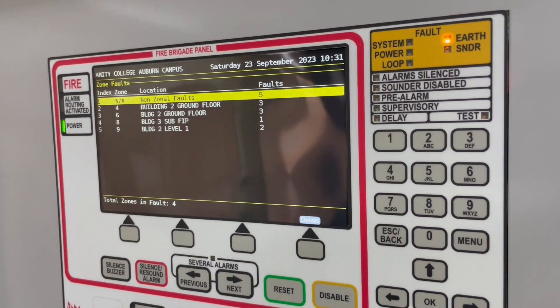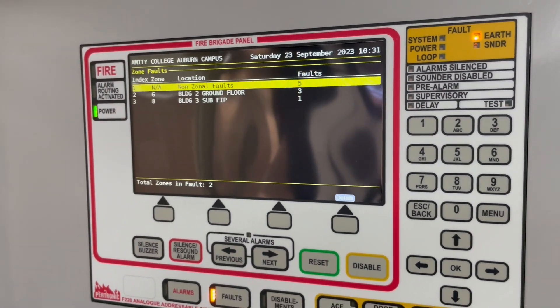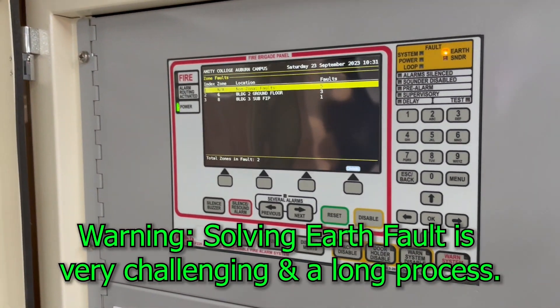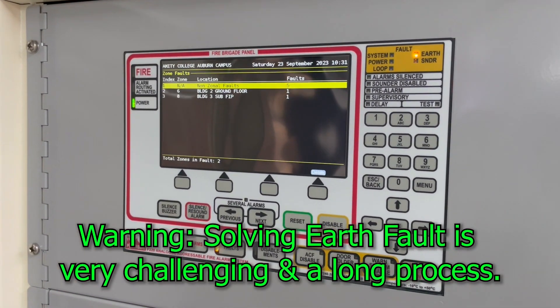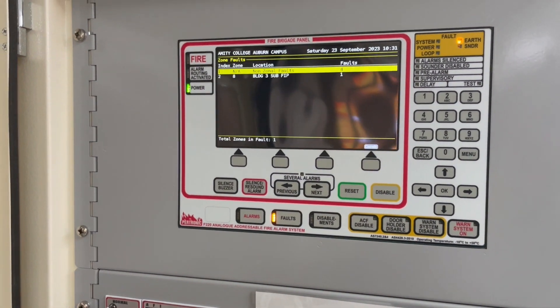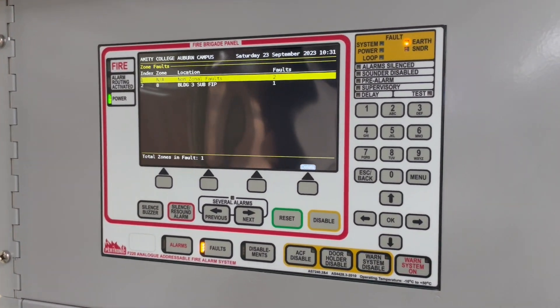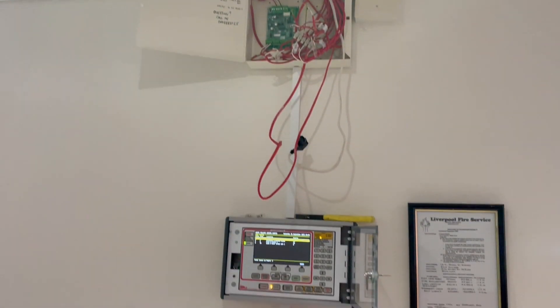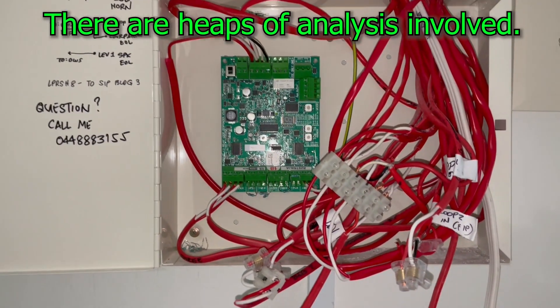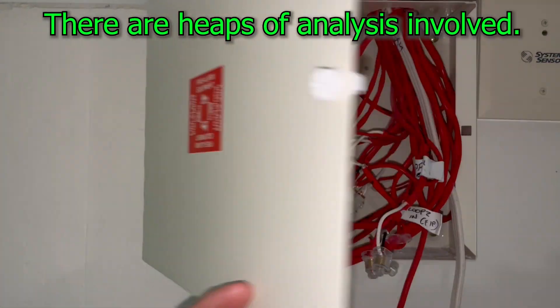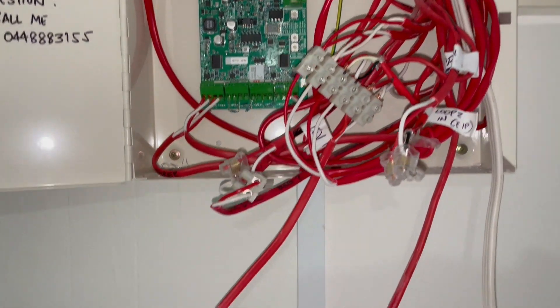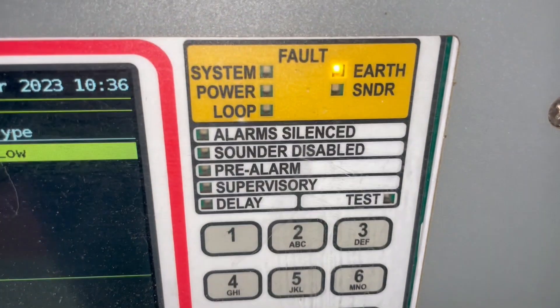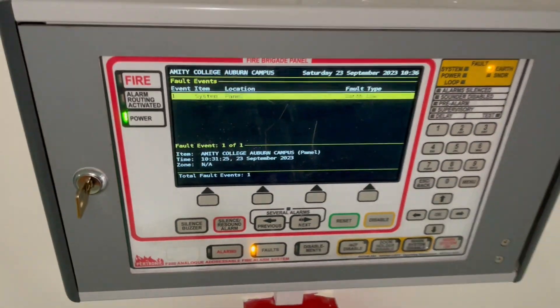Let's go around and have a quick look if there is no other visible problem. And then we are going to do something else in one of the junction boxes. This is where we're working right now. We are in one of the junction boxes. Luckily it's just below the mimic panel, so we can check the earth fault. We don't need to go to the main fire panel.